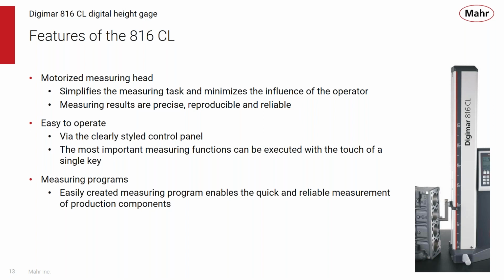We say it's very easy to the operator. So I pointed out the single key operation. They're very clearly stylized on the control panel, and most of the functions can be executed with the touch of a single key. If you have a number of parts that you're going to be measuring, you have a production run and you have a series of parts, you can teach the 816 and create a program that enables quick and reliable measurement on those production components. So once you go through a measuring routine once, you can save that measuring routine and pull it up and do it again. So it's very easy to do. And what will happen is as you begin the measuring routine and move from one length to another, the gauge will move to the next position, and you tell when it's ready to go, it'll go down and do that automatically. There's no moving of the slide. The 816 will do it automatically for you.